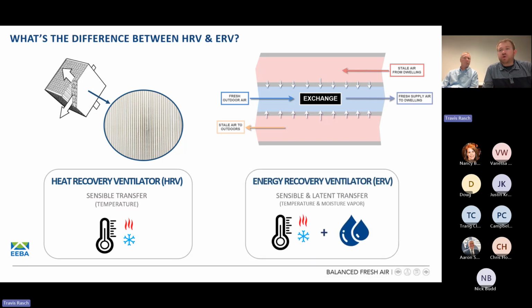The other is an ERV, or energy recovery ventilator. Honestly, over the last few years, and probably over the last decade or so, we've seen a significant shift from HRV to ERV technology. The key is that not only do you get the same sensible transfer, but you're also getting a latent transfer, or moisture vapor. So we're kind of getting the best of both worlds. We're getting the sensible transfer we got from the HRV, but we're also adding this latent component to it. To be honest, the cost of these two products has become much more in line than it had been in maybe the last 5 to 10 years. So the popularity of ERV has jumped up significantly, again because you're getting the benefits of both temperature and moisture vapor transfer.